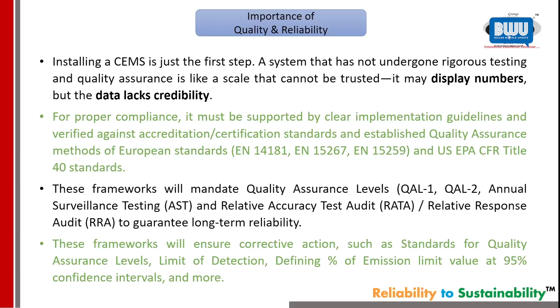So these are the key standards on which our system's testing was performed. Again I repeat, I'm presenting this with a case study where our system went through testing to the European standard. So the quality and reliability of CEMS performance was per EN 14181, wherein QAL 1, QAL 2, QAL 3, and AST. Not many people in this audience must have heard the QAL 1 word. "QAL 1 chahiye humko, QAL 1 certified chahiye." Now, after 30 minutes, probably you will say that no, we don't want certified equipment. We want tested equipment, which comes with a test report, where I can understand what the drift values are and how my linearity values are differing. So this is more important than having a piece of paper of certification. So these are the standards. I'll be talking more about 15259, a very primary important standard.